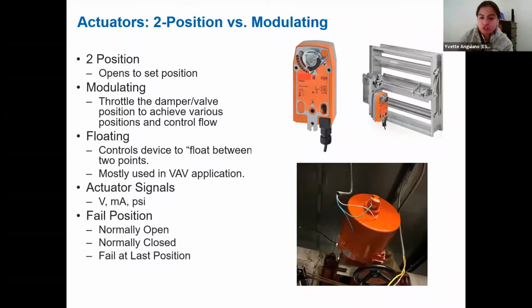This isn't the preferred control for dampers in an air handling unit setting, but you can see those more in a terminal unit setting, such as a VAV application. And then in terms of the signals used for these actuators, previously the controls industry used pneumatic controls, or that pressure control, which is why you'd see that PSI signal. Nowadays, you're using volts or amps. For modulating signals, that signal can range from 2 to 10 volts or 4 to 20 milliamps. And these values are important in terms of how you want to see your system react to those specific values.